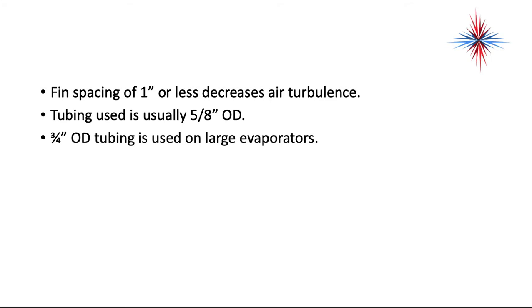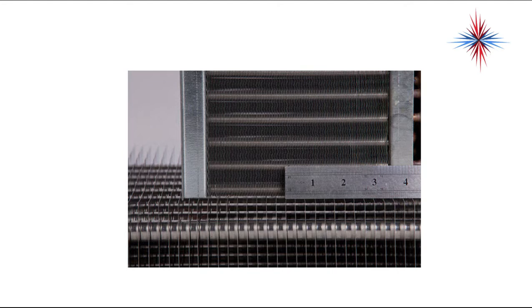Evaporators with 6 to 8-inch depth usually have 1-inch spacing; those with 18 to 20-inch depth often have 1-and-a-half-inch spacing. The tubing in an evaporator is usually 5/8-inch OD, while 3/4-inch OD is used on large evaporators. The bottom evaporator has much wider spacing than the top evaporator. Closer-together fins have more surface area but restrict airflow, while wider-spaced fins have less surface area but allow more airflow to move through faster.